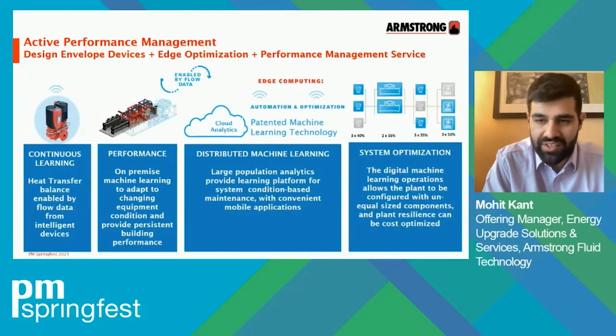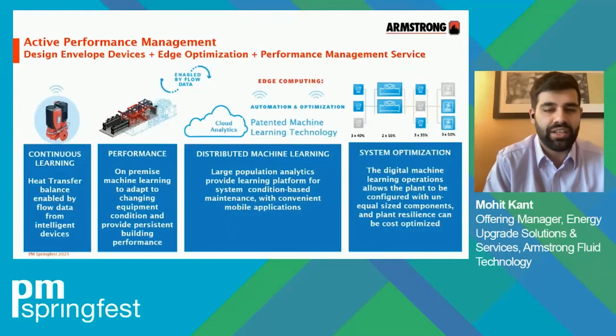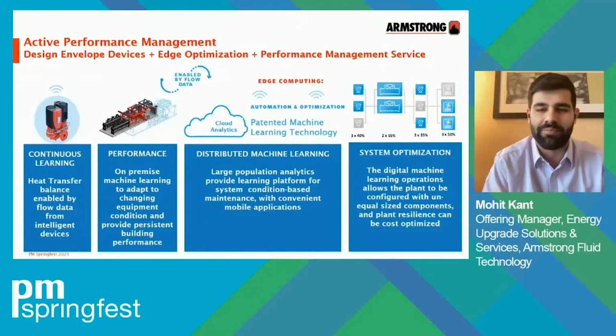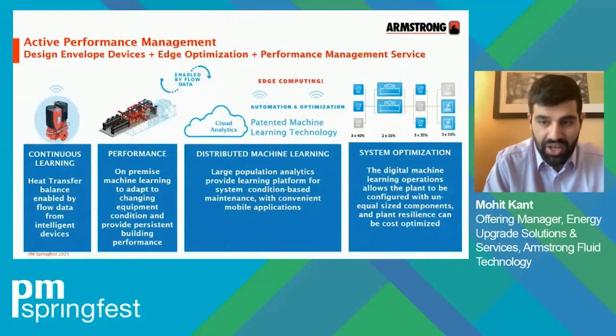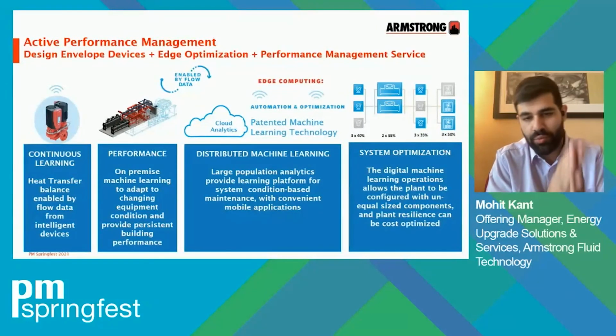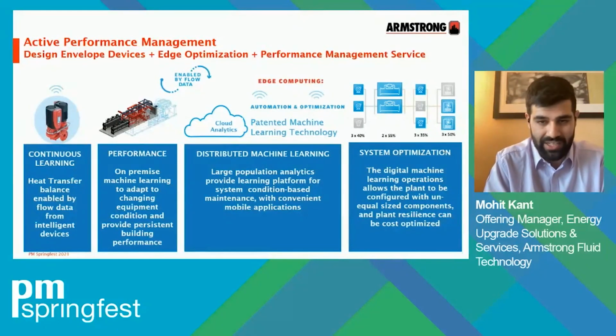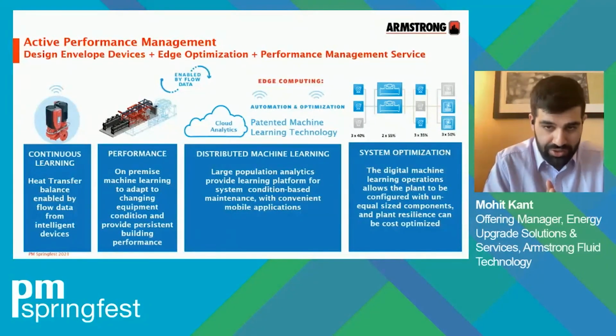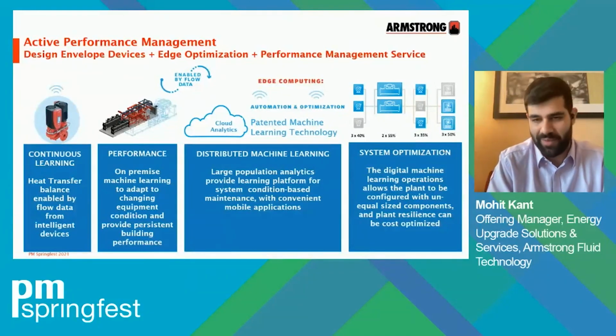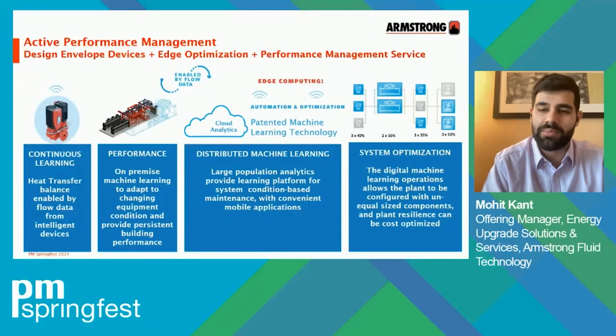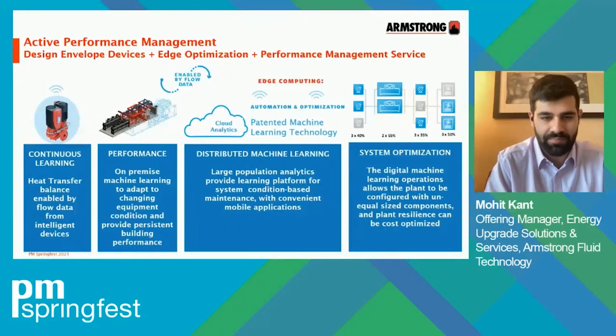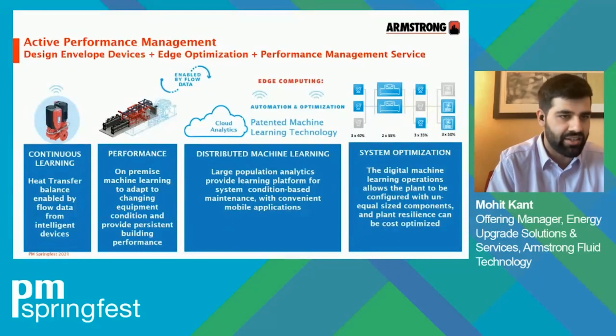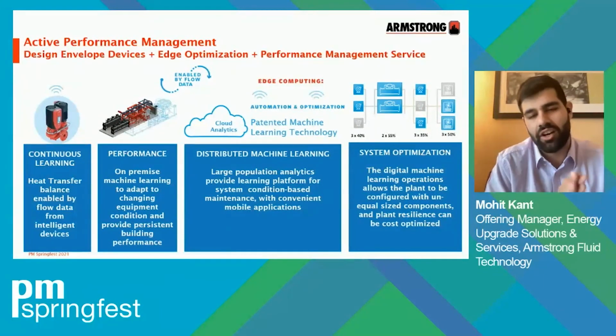In the top right corner, we illustrate this concept. A traditional plant would have 3 of each major component, including distribution pumps, chillers, condenser pumps, and cooling towers, sized at 50% of max capacity. With the digital approach, 30% first cost savings are achieved by a combination of equipment: 3 distribution pumps sized at 40% of max capacity, 2 chillers instead of 3 sized at 55% of max capacity, 3 condenser water pumps sized at 35% of max capacity, and finally the cooling towers, as in the original plan, sized at 50% of max capacity.